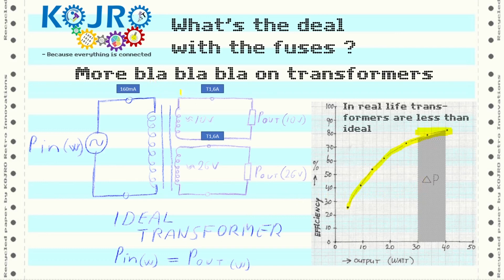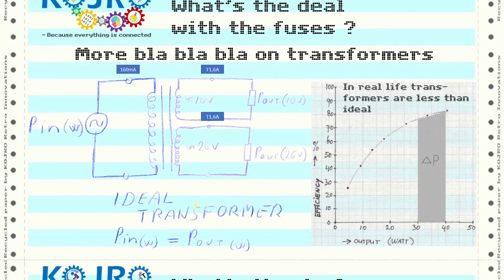That means the rest of the power going in will get lost in the form of heat, and in some cases vibrations, because these transformers tend to vibrate somewhat. This heat will make a power draw on this fuse, but not on that fuse, because it's lost in the circuit before it reaches these two circuits.